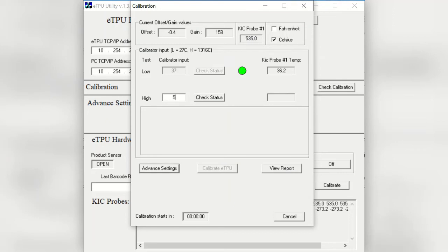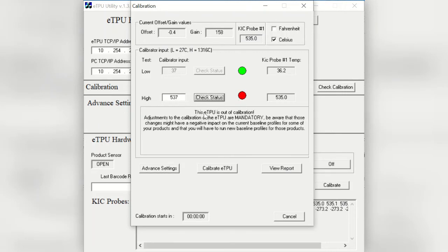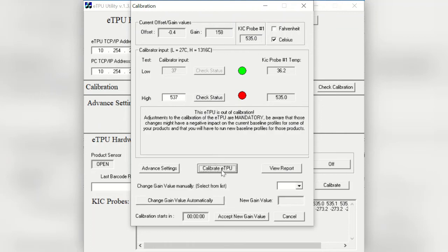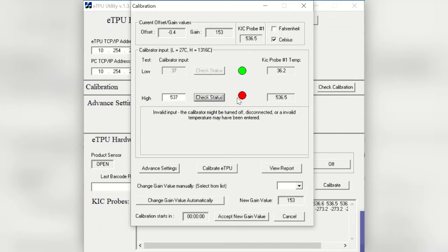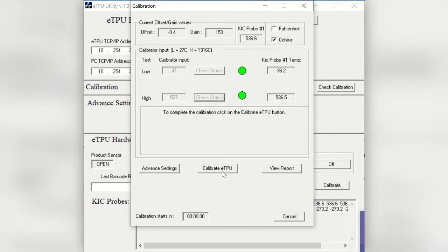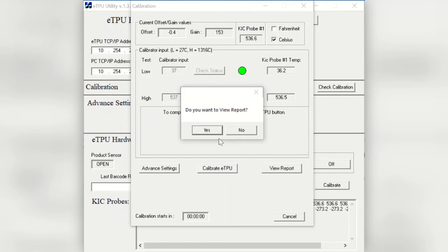Now that the lower limit is calibrated, it's time to move to the higher limit. As before, set your calibrator now to the higher limit and write the same value in the utility and check the status of the calibration. Once again, we are out of spec. Please follow the same steps as before. Click Calibrate eTPU, change gain value automatically, and accept new gain value. After the value was successfully changed, we can see that we are now back in spec. We follow the instructions, click on Calibrate eTPU button, and now it allows us to view the report and print it as a PDF.